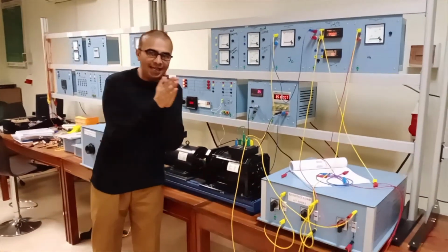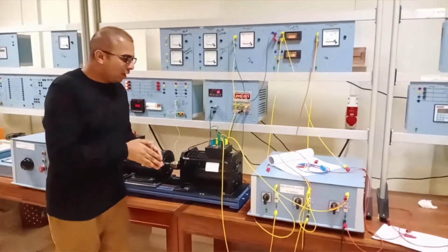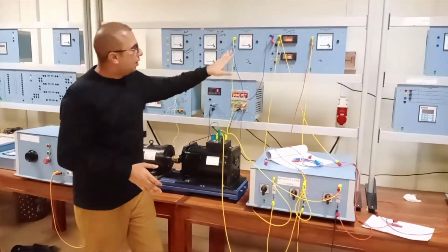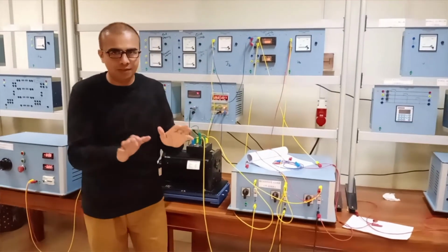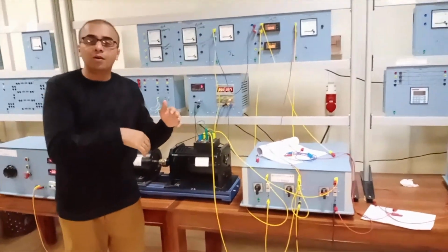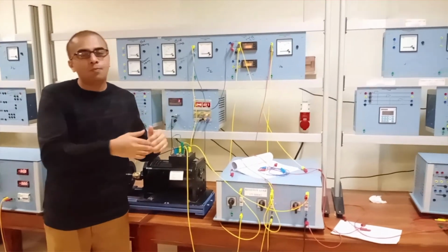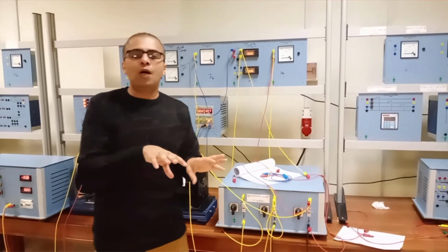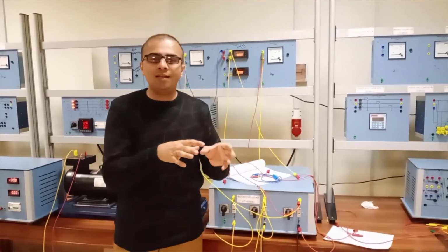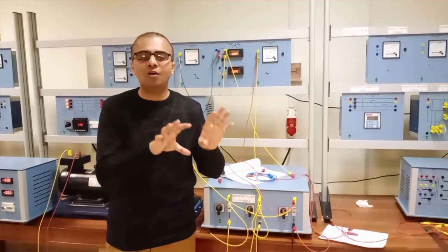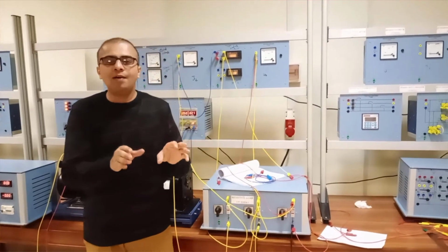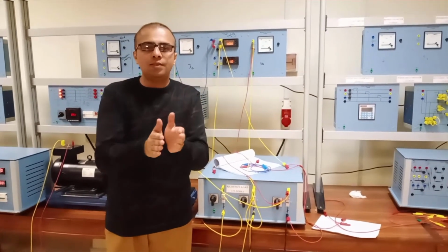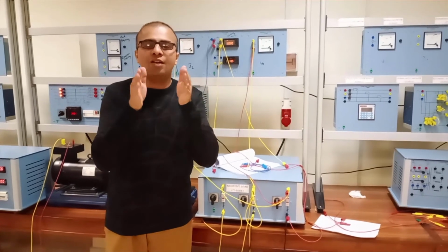We have analyzed from this experiment that if you put load on the alternator, your stator current increases and your terminal voltage falls. This was the load characteristics. But at any point of putting the load, the power factor was unity. From this experiment it is concluded that if you increase or decrease the resistive load, there is no effect on the power factor of the alternator. Why? Because with a resistive load, the power factor of the machine is unity, since the voltage and current are in phase with each other.